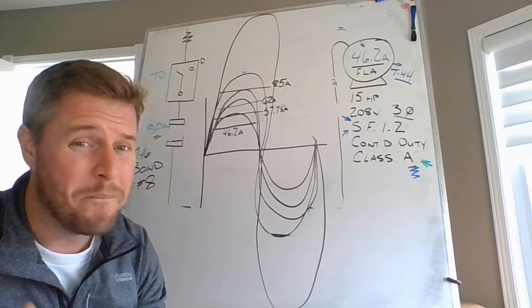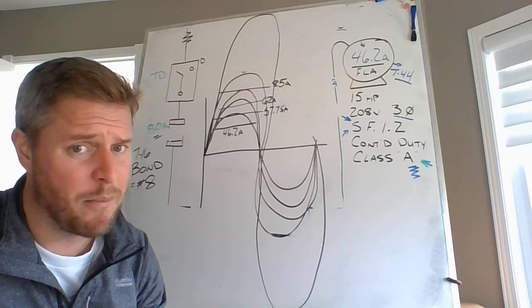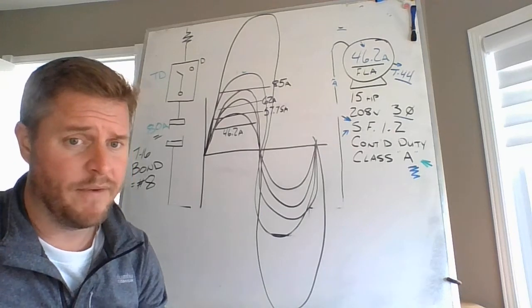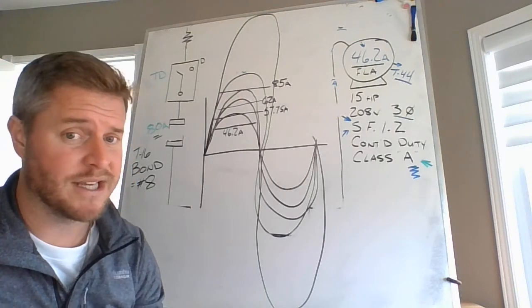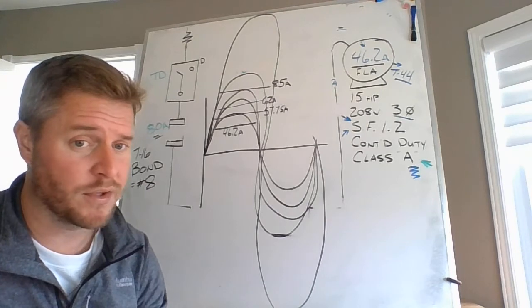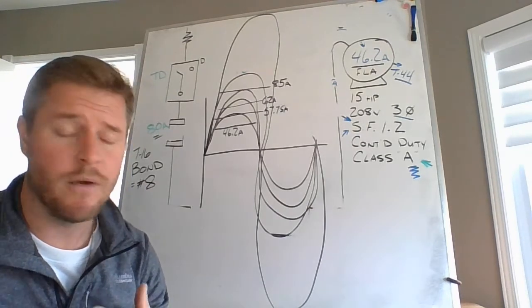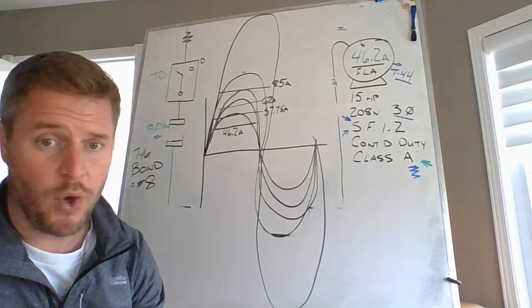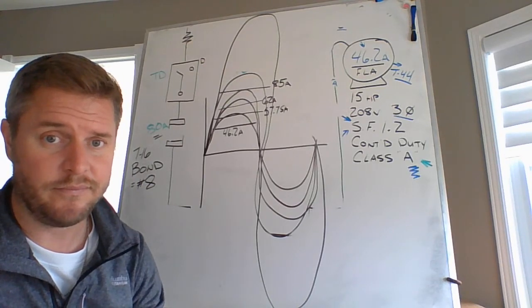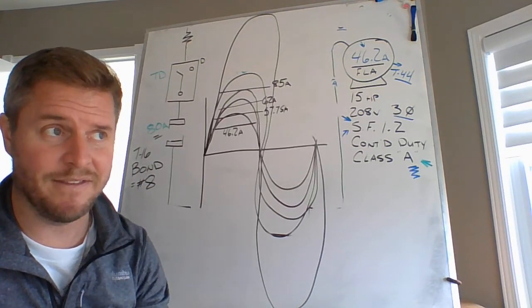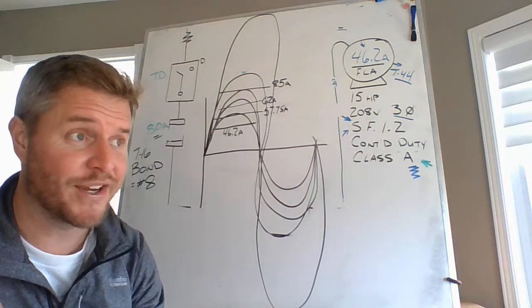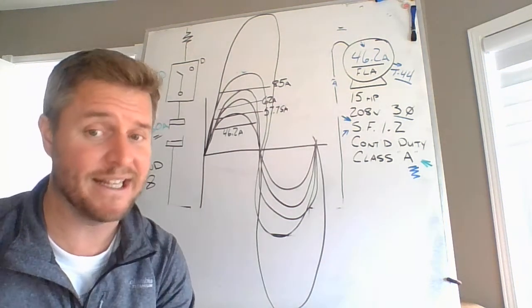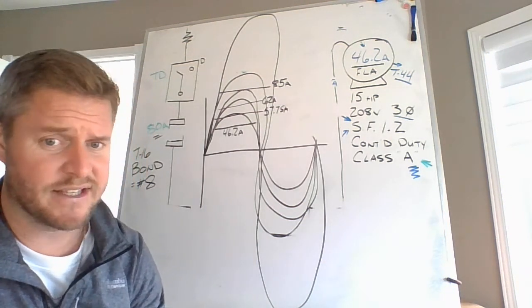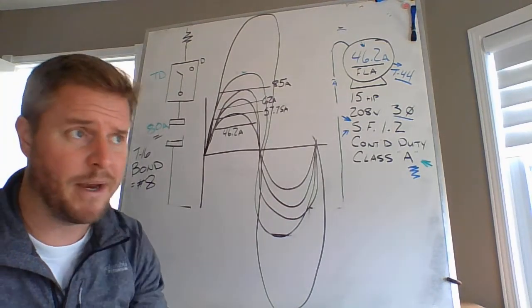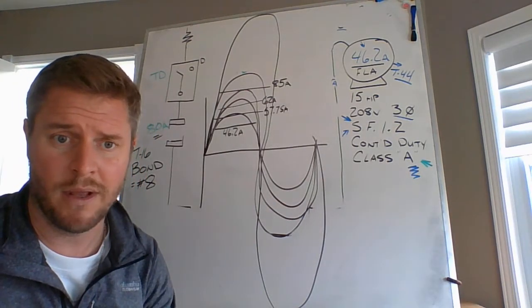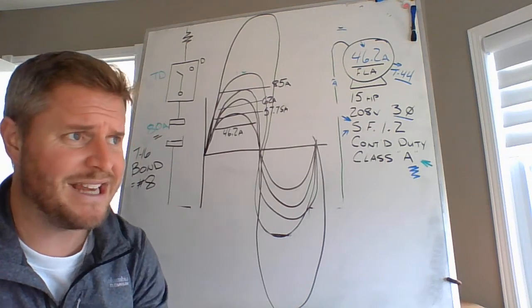Maybe 1 ohm, and that's a maximum, maybe 1 ohm. And if it's a 1 ohm resistance in that wire on a 208 volt circuit, that means that 208 amps will want to flow. But that's a maybe, because it's an AC circuit. So now you're talking about impedance, not so much resistance anymore.